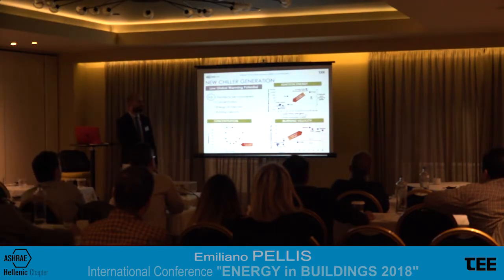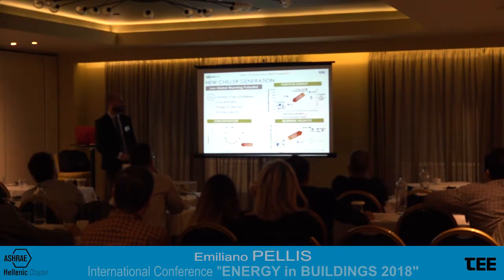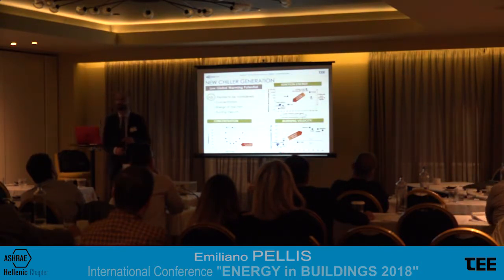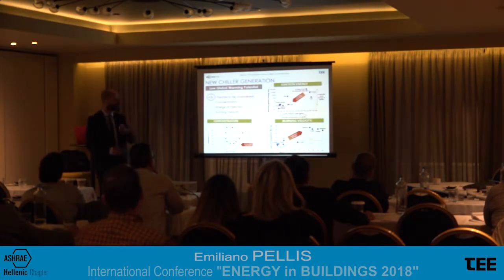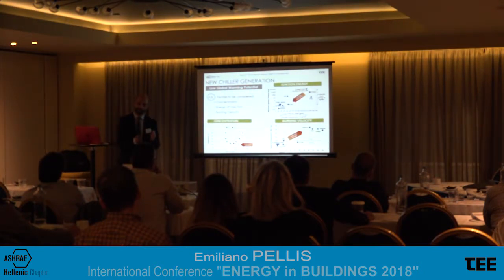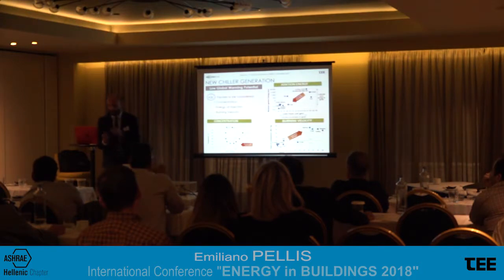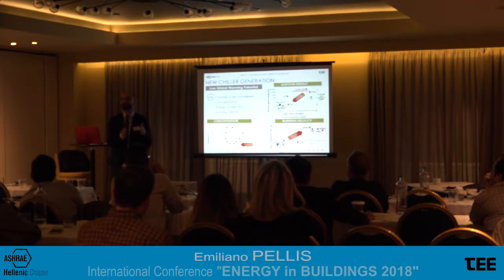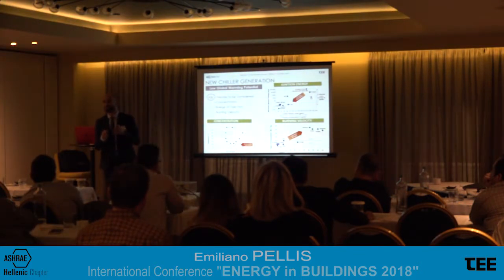Last element, the burning velocity. The burning velocity for the A2L class refrigerant is very low, below 10 centimeters per second. This means that even in the unlucky case we have a flame, it will likely auto-extinguish. So all of this to say that A2L class are a good alternative to standard refrigerant. They are safe, and consider that the concept of A2L class refrigerant is now embedded in the standard EN378, which is the standard that all the manufacturers follow for the design of the unit.